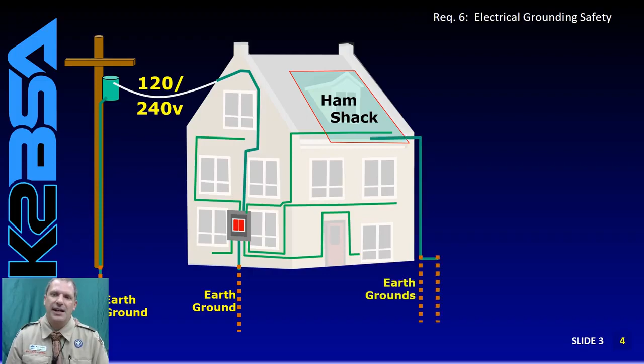Grounding will be different depending on the kind of soil you have. Loam and clay is good. Sand and rock, not so good. Some ham shacks have separate ground wires attached to the home's cold water pipes like this one. The idea is that the cold water pipes eventually run through the earth ground. Hot water piping may be isolated at the water heater from the earth ground, so it should never be used for this purpose. Natural gas lines also should never be used for grounding.